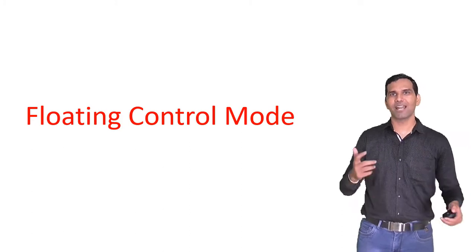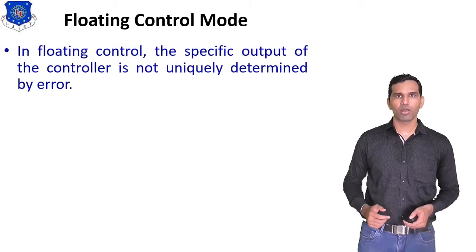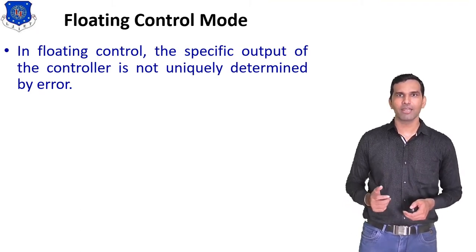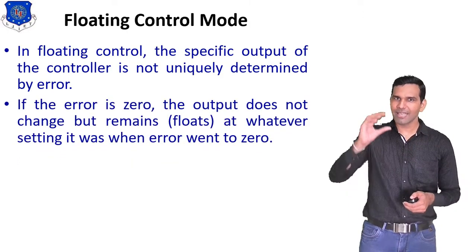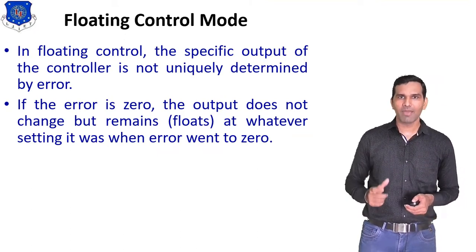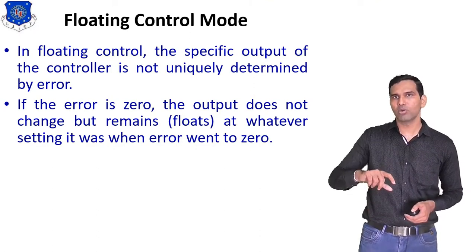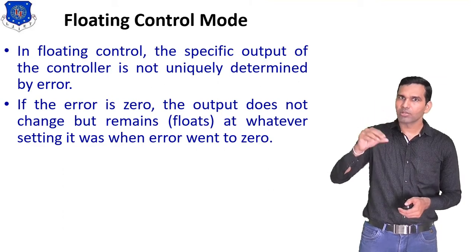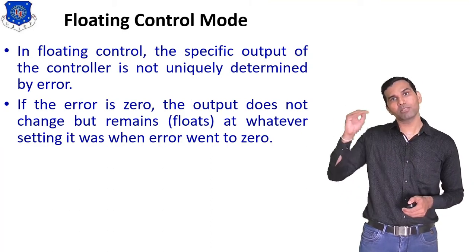Without wasting time, we start with floating control mode. In the floating control mode, the specific output of the controller is not uniquely determined by error. If the error is zero, the output does not change — it does not go to zero.